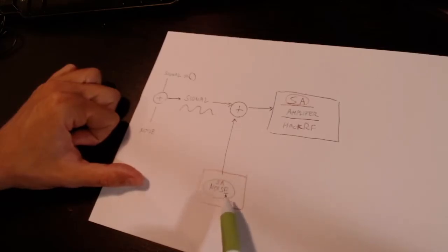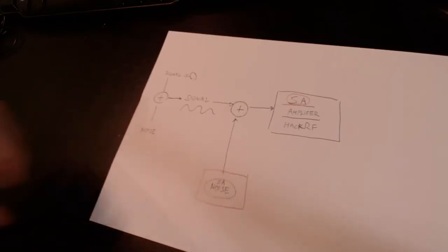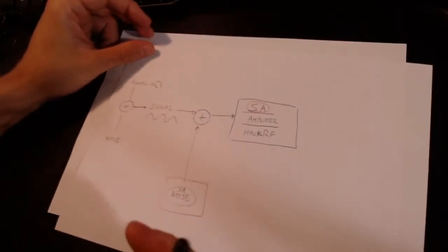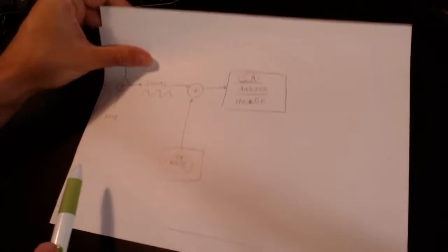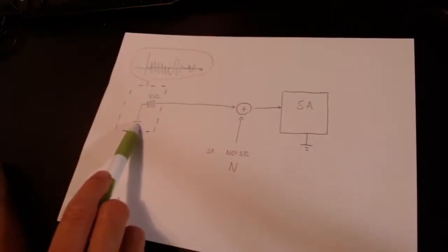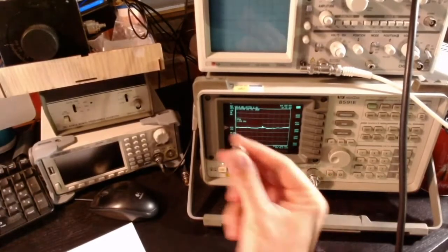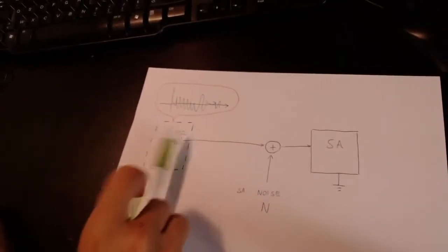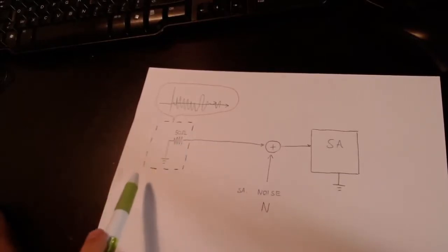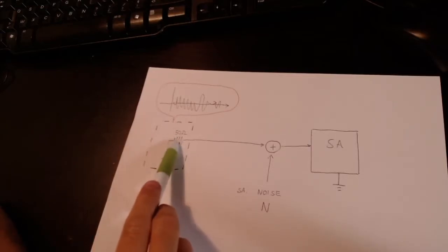How can we measure the strength of this internal noise? The basic idea is to prepare a setup where the signal and associated noise coming into the input are known. A convenient way to do this is to terminate the input of the spectrum analyzer with just a resistor — a 50-ohm resistor. Looking at my spectrum analyzer, this is exactly what I've done: there is a small dummy load, which is a 50-ohm resistor, plugged at the input.